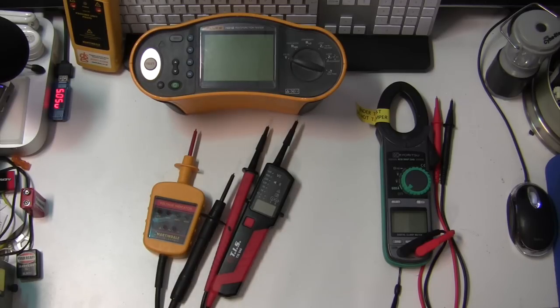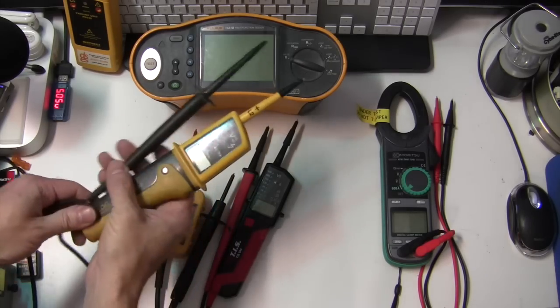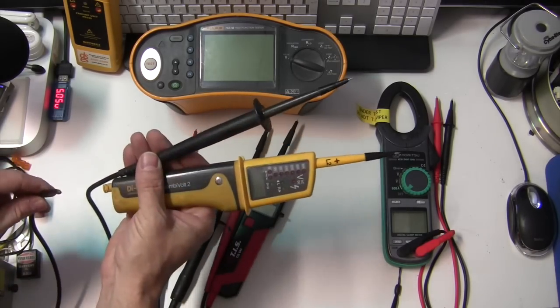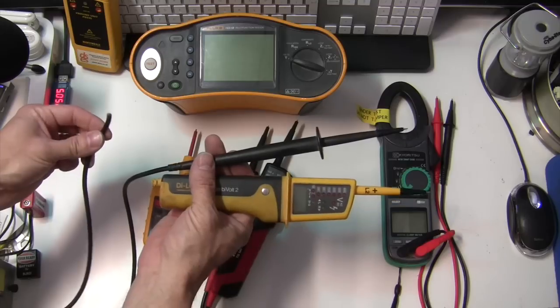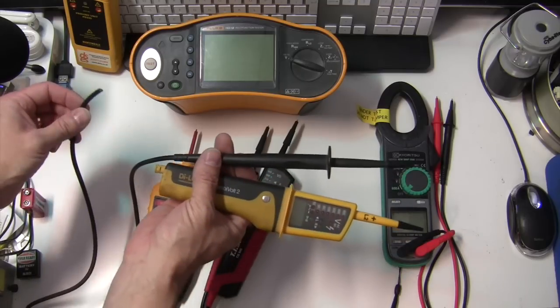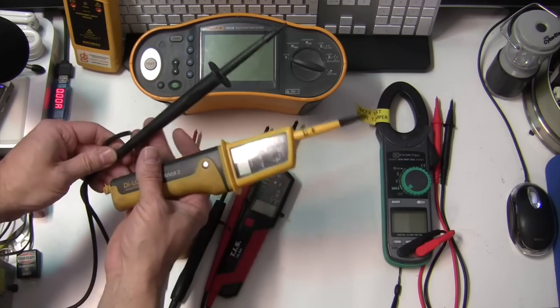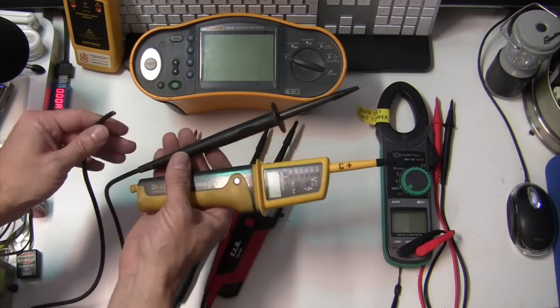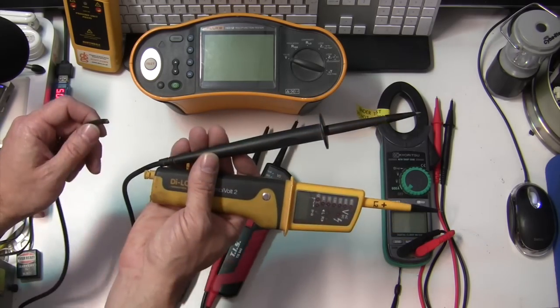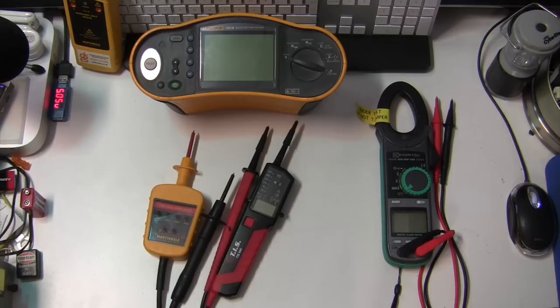Let me show you my old Di-Log voltage indicator—this was my go-to contact tester for five years. Then one day the probe cable just dropped out of the end, just like that, no warning, no problems using it until the day it fell apart. Wear and tear does take its toll, and if there are any signs of damage, especially if live parts are exposed through cracked casings or damaged wiring insulation, then it's time to replace it with something new.